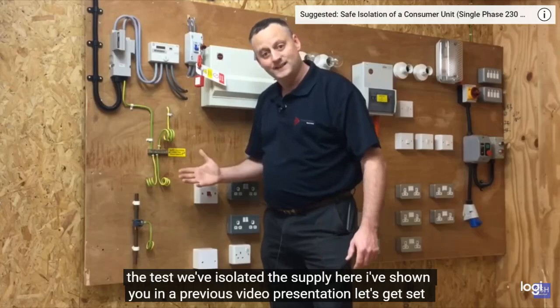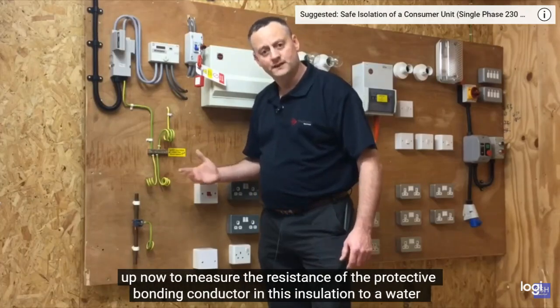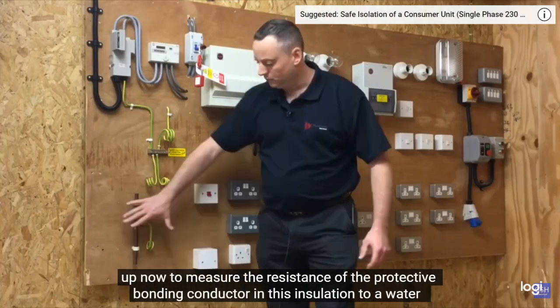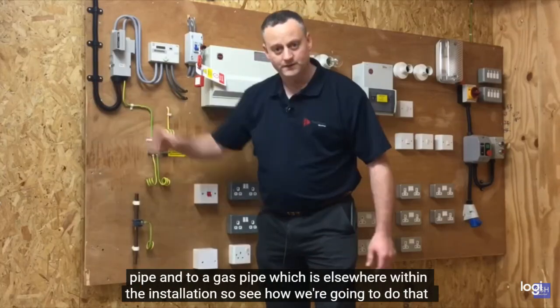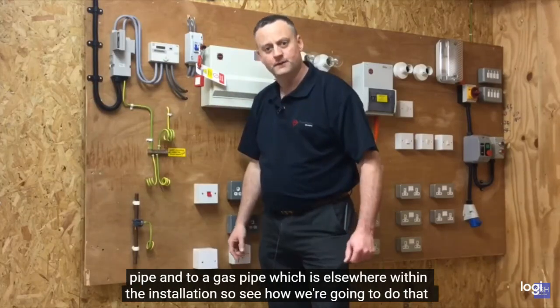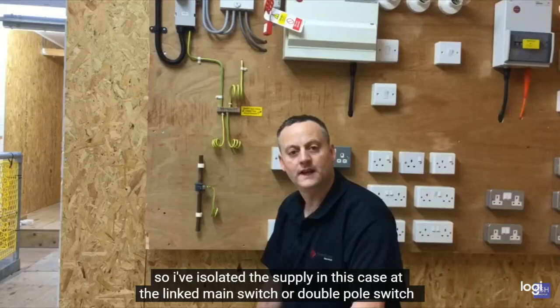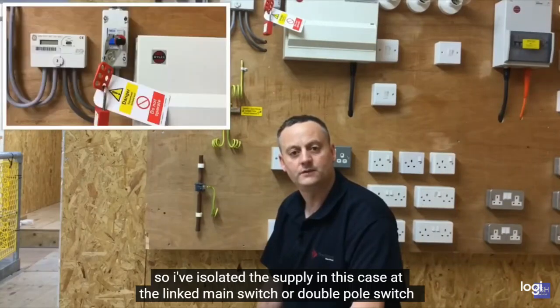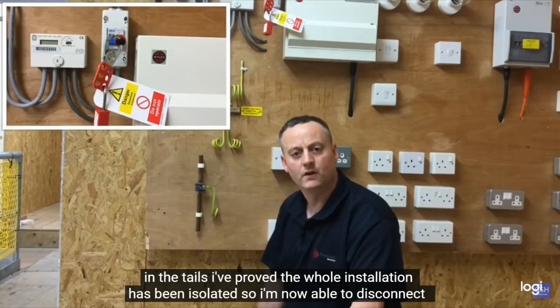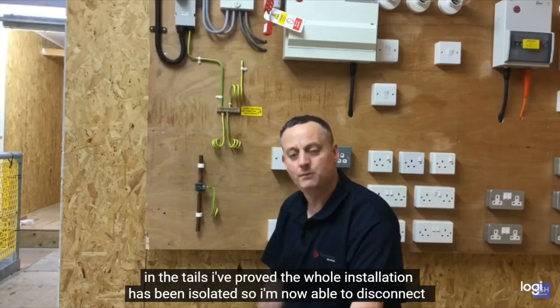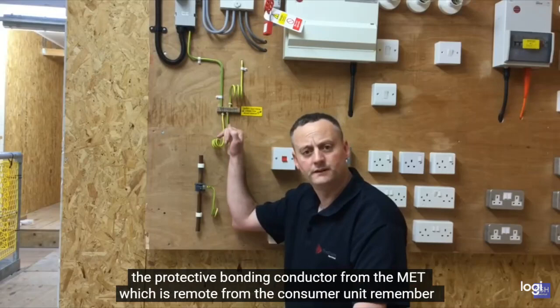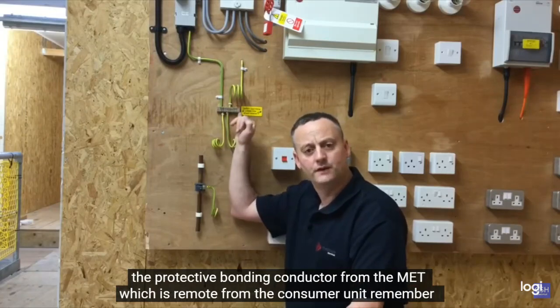Let's get set up now to measure the resistance of the protective bonding conductor in this installation to a water pipe and to a gas pipe, which is elsewhere within the installation. So let's see how we're going to do that. I've isolated the supply, in this case at the linked main switch or double pole switch in the tails. I've proved the whole installation has been isolated, so I'm now able to disconnect the protective bonding conductor from the MET, which is remote from the consumer unit.